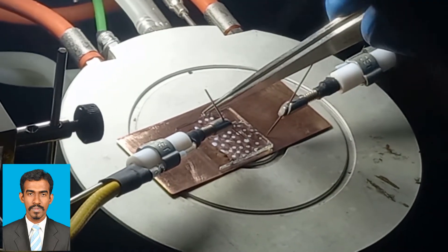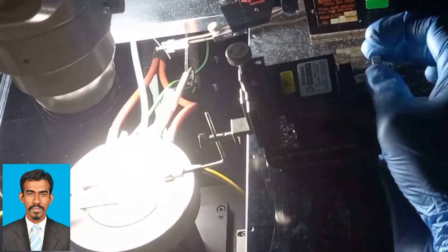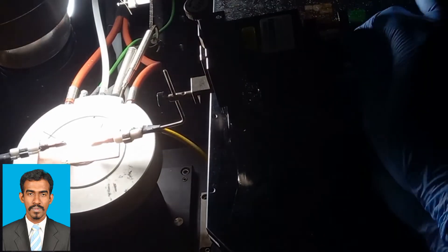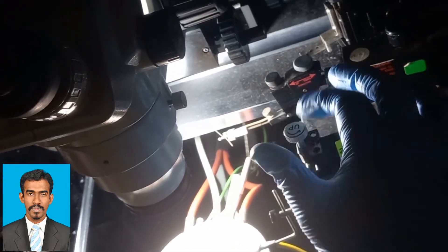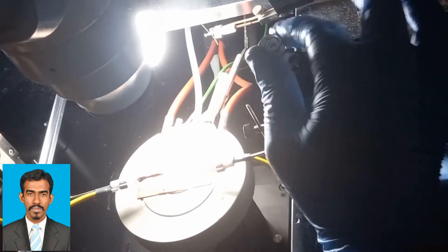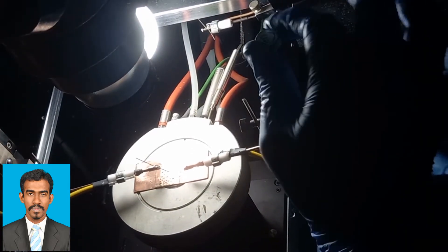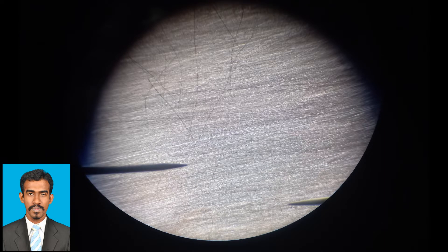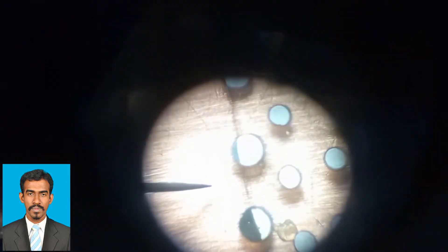I am placing my sample on the probe station. With the help of the microscope I will position the needles on the desired points. I am moving the needles with the manipulator — this knob moves the needle up and down. Now I am probing using the down button. I am almost done with probing. You can verify through the microscope — the probes are now connected properly on the desired points.